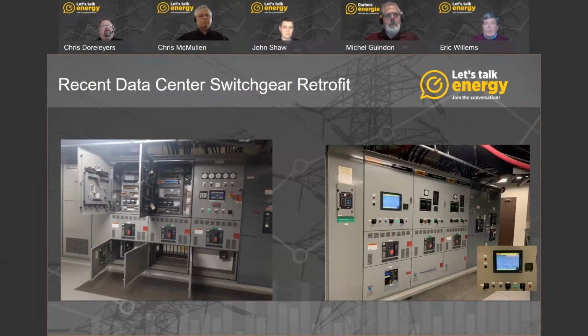The second panel with an open door contains the synchronizing controls and the protective relaying for generator 1. The large control device in the center is a Woodward synchronizing controller. Many of the components inside this panel are obsolete and do not have direct replacements with matching footprint and terminal block arrangements. Every component in this panel is critical for the parallel operation. If any one of these components fail, it will take time to redesign and rewire the back panel to install the replacement device. Because these electronic components are 21 years old, the risk of failure is high and the downtime would be significant. Over to you, Chris.